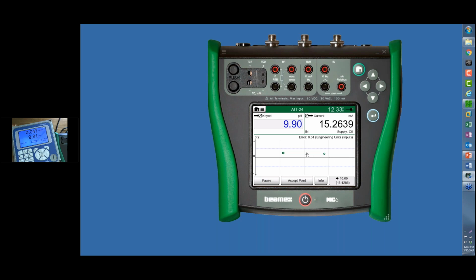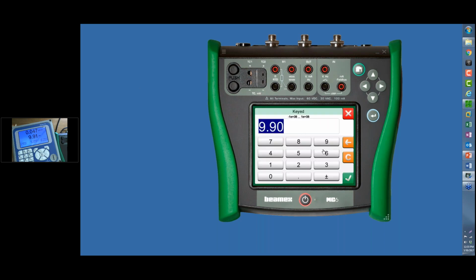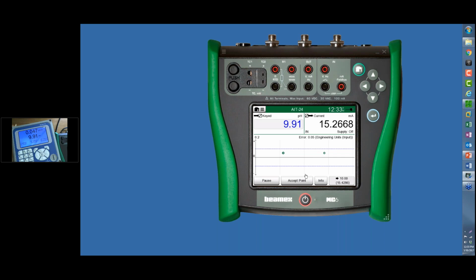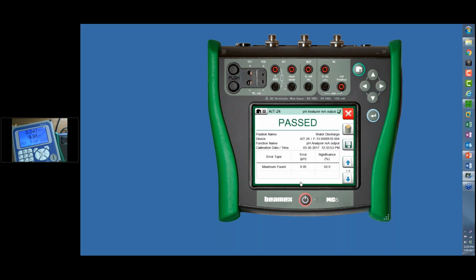And I'm just going to take this right now. Well, you saw that we just changed to 9.91. And if I waited another 5 minutes or longer, it would continue to climb up to 10 pH, as my testing has shown. But for the sake of time, we're not going to allow that. So let me accept this point. So we passed. Our maximum error was 0.05 pH.